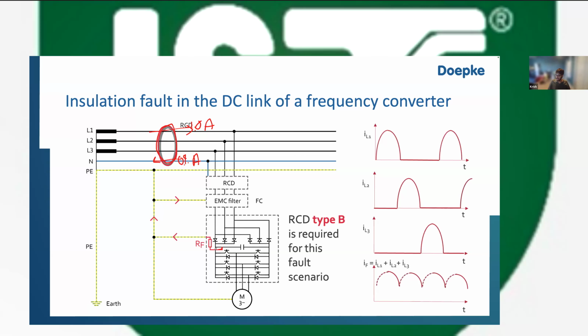When you have DC current, which is what happens in this particular case, this component here is the DC component. From basic elementary physics in school, we know that when a DC current, which has no changing magnetic field, flows through a coil, it will become magnetized, but there will be no net current induced. Because of that, the device does not disconnect, as there is no net current in the toroid. So you need sophisticated equipment to filter out that DC component and then use it to signal, or if it is purely DC, to detect that DC and send a trip signal.